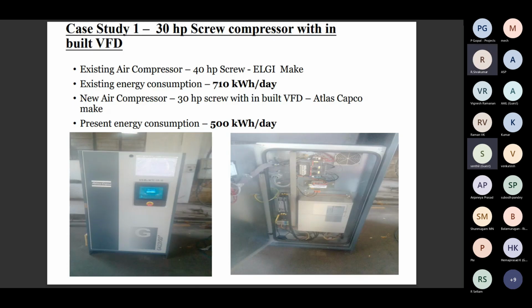Next one: the existing 40 HP compressor was replaced with a 30 HP screw compressor with inbuilt VFD. The old 40 HP compressor consumed 710 units per day. The new compressor consumes only 500 units per day. Next.